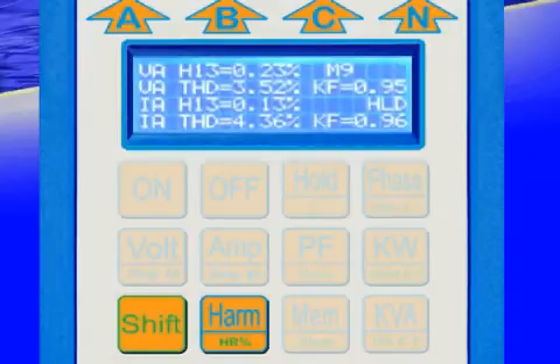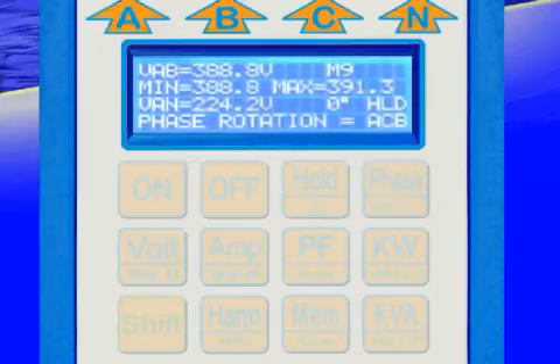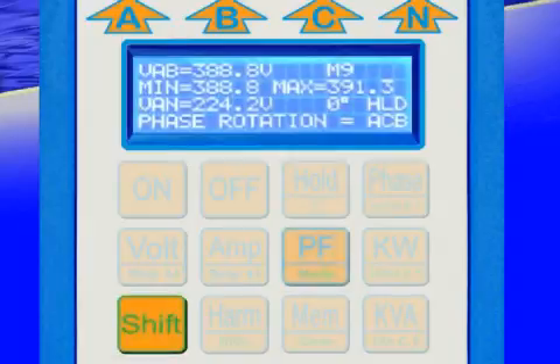Now that you have successfully performed an energy audit, you can continue on by taking a power analysis. Before using the power analysis mode, you should always perform an energy audit to confirm that CT and voltage connections to the load are correct. To change from energy audit mode to power analysis mode, press and hold Shift Mode until the desired mode is displayed.